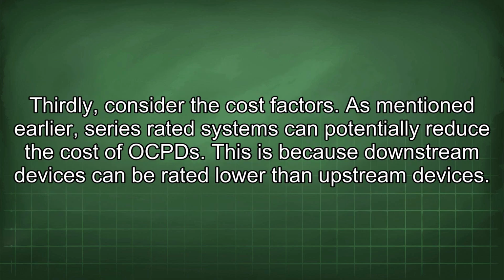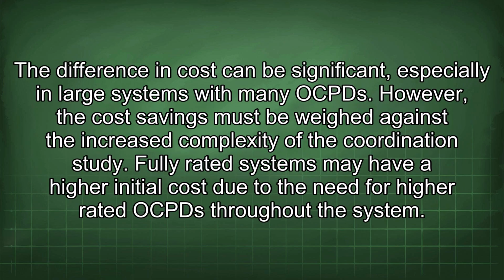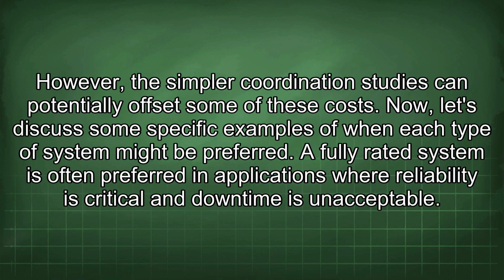Thirdly, consider the cost factors. As mentioned earlier, series-rated systems can potentially reduce the cost of OCPDs. This is because downstream devices can be rated lower than upstream devices. The difference in cost can be significant, especially in large systems with many OCPDs. However, the cost savings must be weighed against the increased complexity of the coordination study. Fully rated systems may have a higher initial cost due to the need for higher rated OCPDs throughout the system. However, the simpler coordination studies can potentially offset some of these costs.